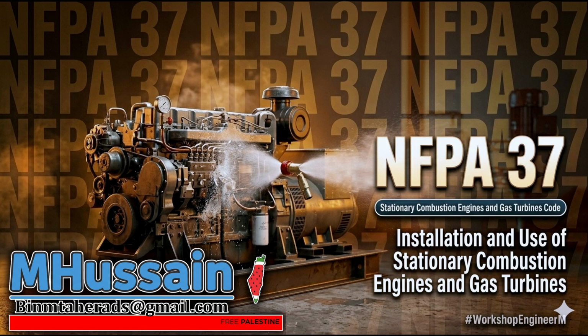Okay, so if NFPA 110 is the personal trainer making sure the heart keeps beating, NFPA 37 is, what? It's the cage, keeping the tiger from eating the spectators. Oh, wow. That is a dark view of the situation. But it's true. NFPA 37 assumes the engine itself will eventually fail. And when it does, it assumes it will cause a severe fire. So it doesn't care if the hospital gets power. Not at all. Its only mandate is containment and isolation. It just wants to make sure that when a fuel line ruptures and sprays diesel onto a hot exhaust manifold, the hospital itself doesn't catch fire.